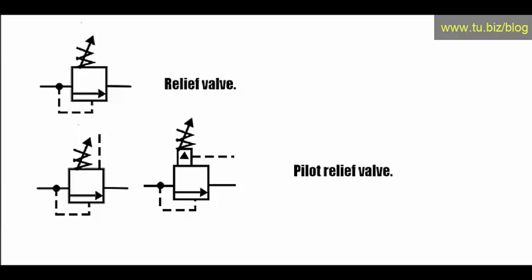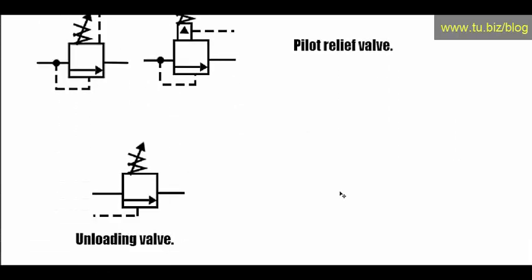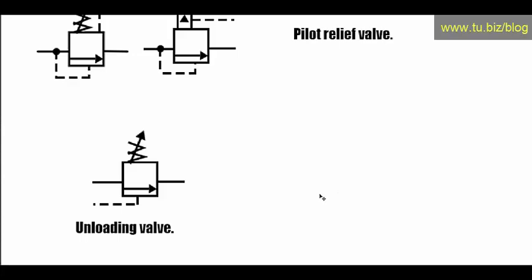Next we have an unloading valve. This valve is drawn very similarly to the relief valve, but the line to open the valve does not come from the same pressure port of the valve — it comes from a different source elsewhere in the hydraulic circuit to open the valve.